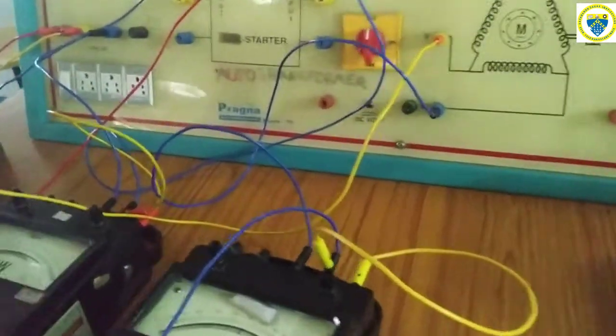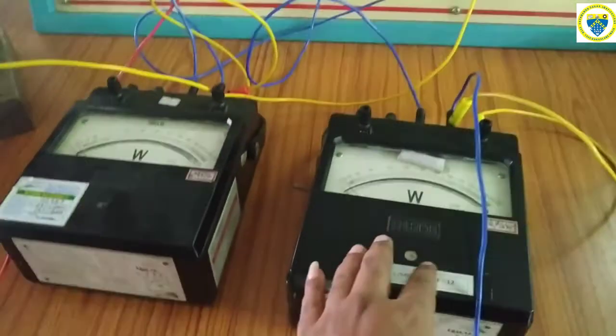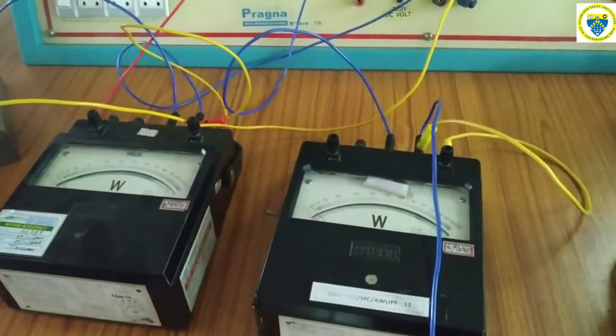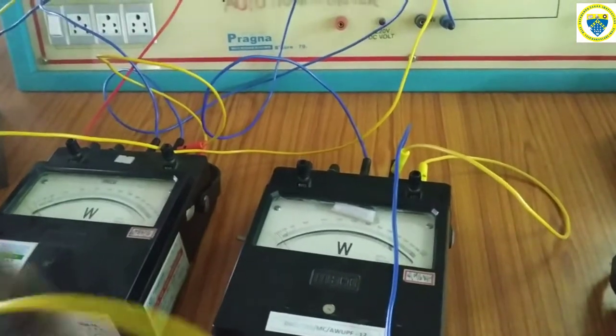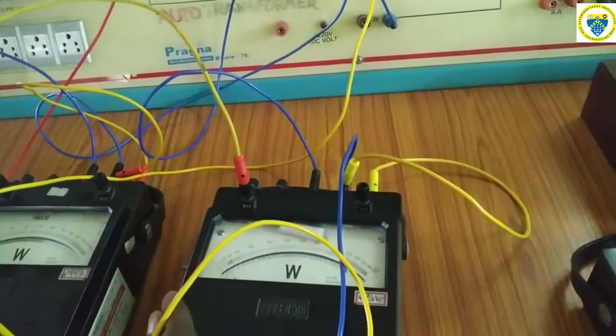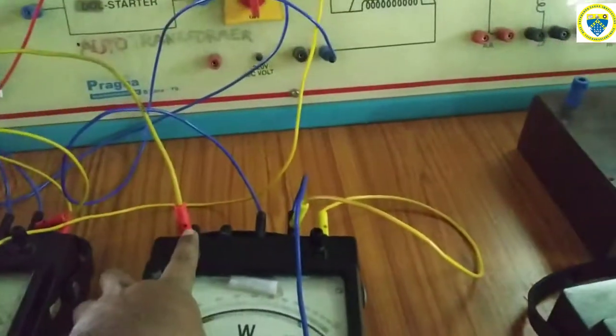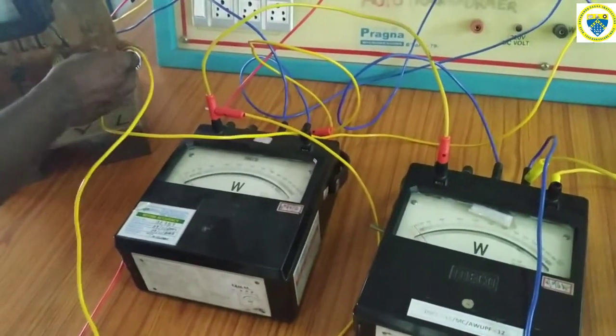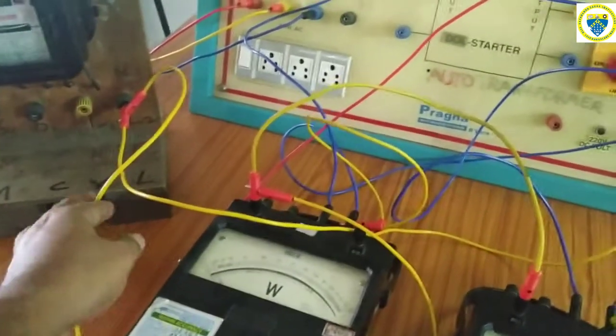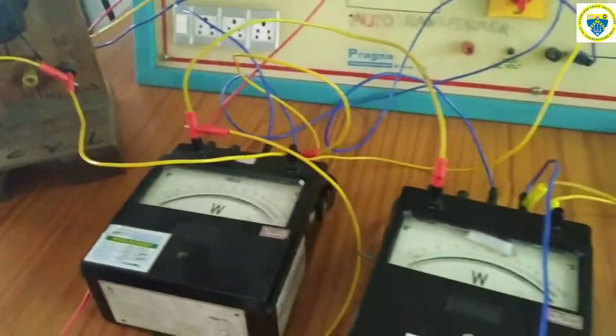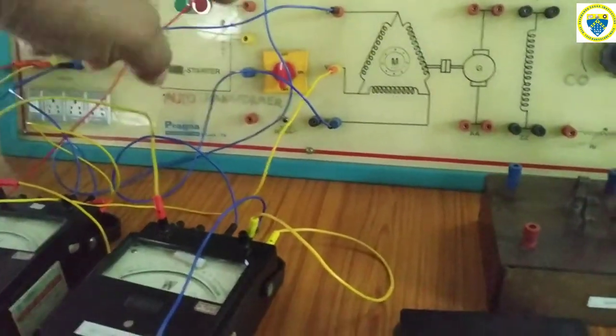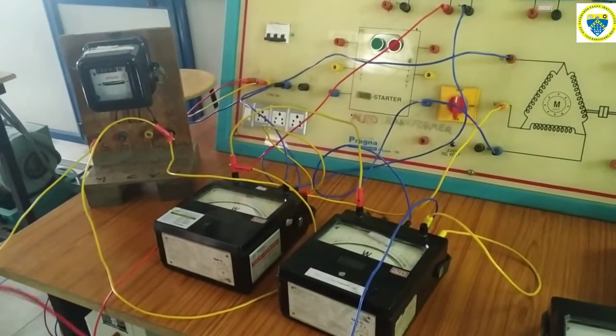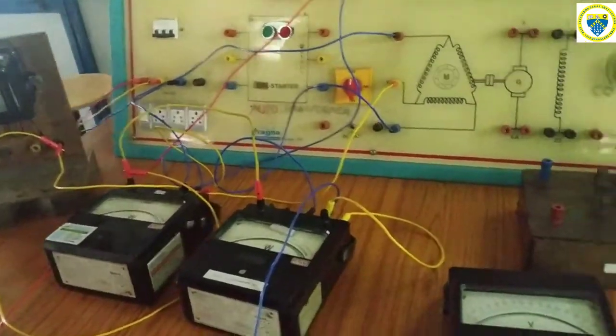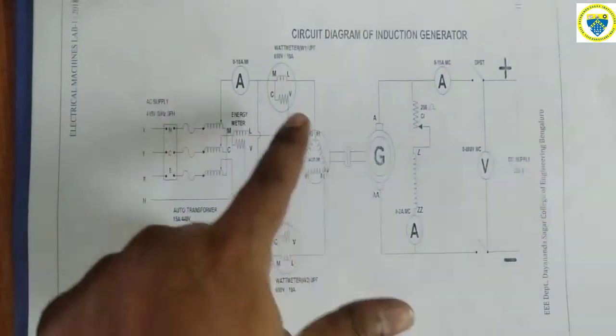Then V and V of both the wattmeters should be shorted, and we are using a voltage range of 600. As V and V of the wattmeters are shorted, one terminal should go to the L terminal of the energy meter. So this is the overall connection at the left hand side, that is, the induction motor side connections are done.